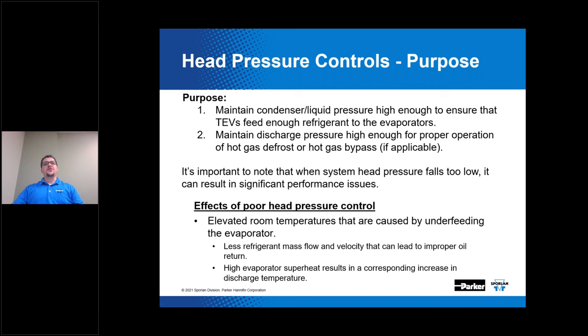It's important to note that when system head pressure falls too low, it can result in significant performance issues. Negative effects include an elevated room temperature caused by underfeeding liquid to the evaporator. Additional symptoms include improper oil return caused by less refrigerant mass flow and velocity. High evaporator superheats also result in a corresponding increase in discharge temperature — a rule of thumb is that for every one degree increase in superheat of the vapor entering the compressor, discharge temperature increases approximately one degree. By designing the system with proper head pressure control, you'll prevent these performance issues during low ambient temperatures.